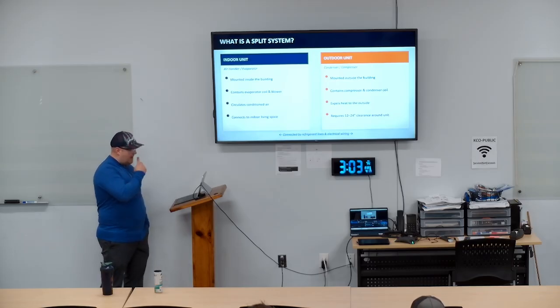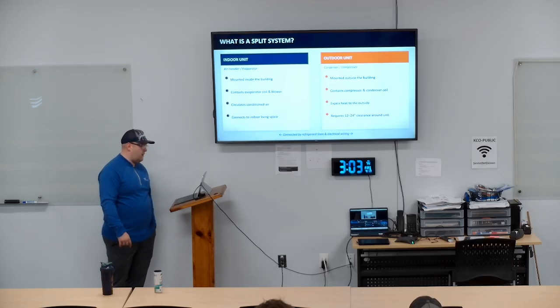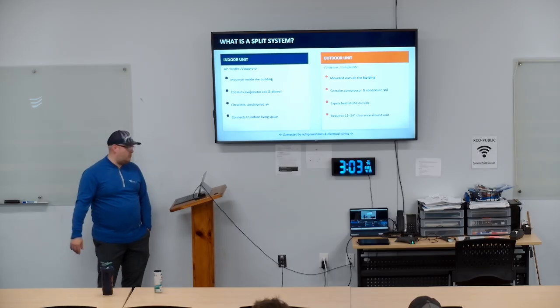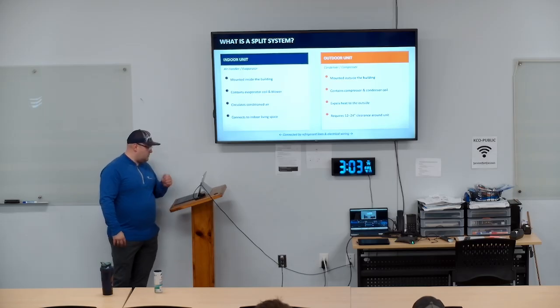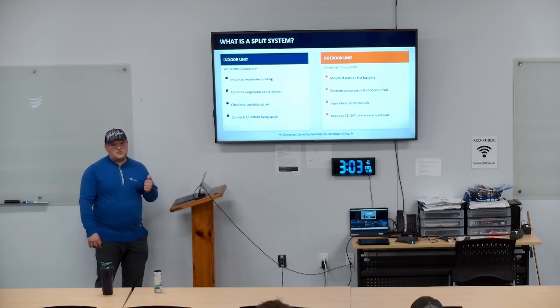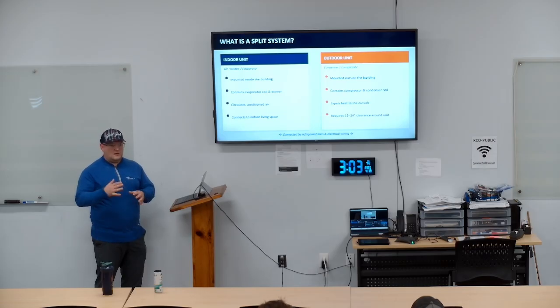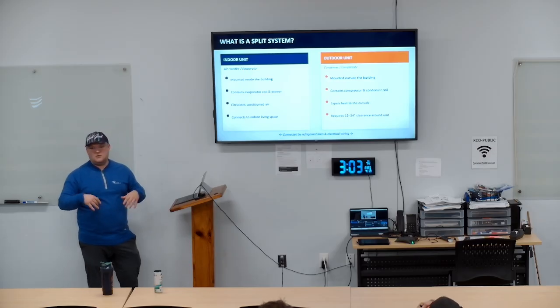The outdoor unit also expels heat to the outside. As it's cooling, the fan is removing heat from the coils. Always check the IOMs. That's where we get our clearances. I know a lot of times people will say keep it this far off, keep it that far off, but the book tells us everything we need to know. In our IOMs, we've set units inside almost completely walled-off spaces with just one access. As long as we have all of our clearances, top and sides, we're good.